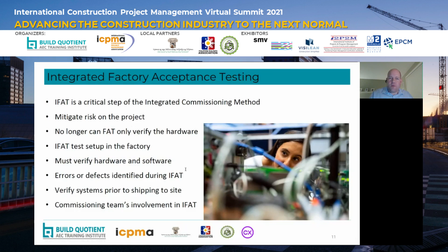Also, if there are issues that are discovered in IFAT, those will hopefully get addressed during IFAT, but invariably there may be some issues that need to be addressed later at site. Having the commissioning team's involvement during IFAT allows continuity between off-site testing and on-site testing for any of those issues that span both sites. So the commissioning team's involvement is critically important during IFAT as well.